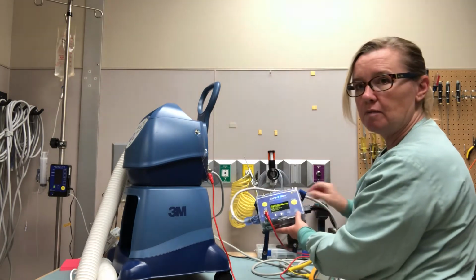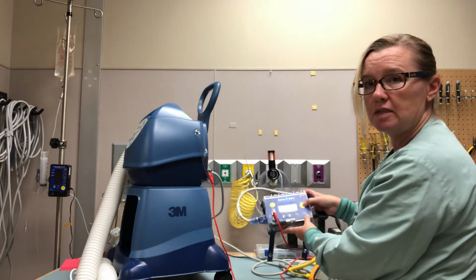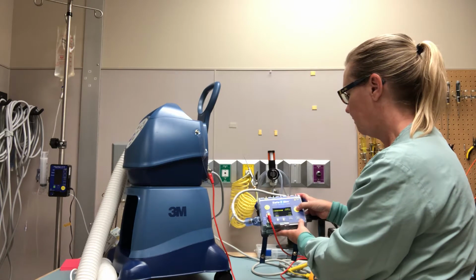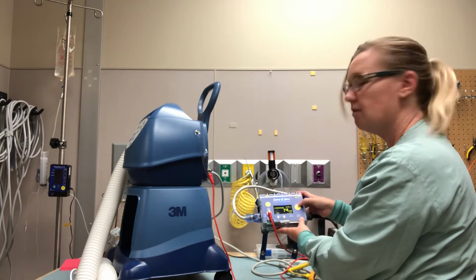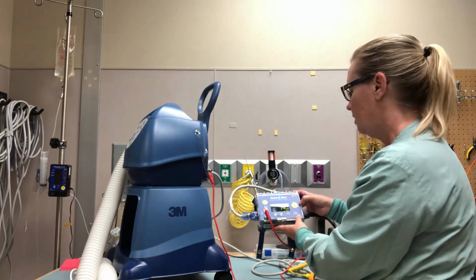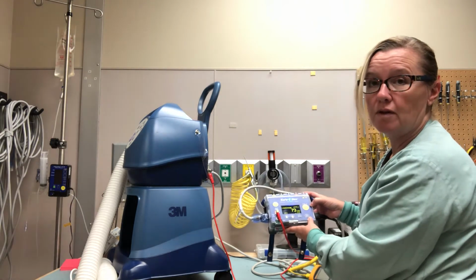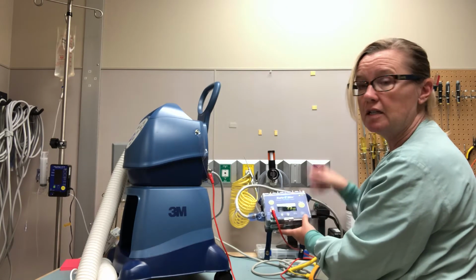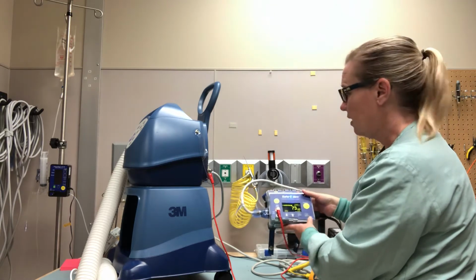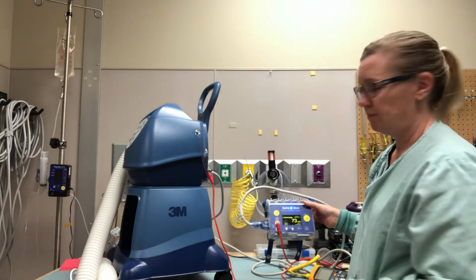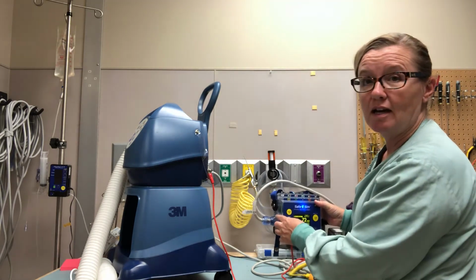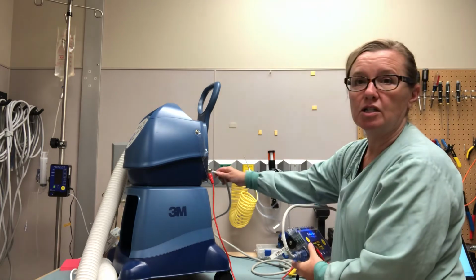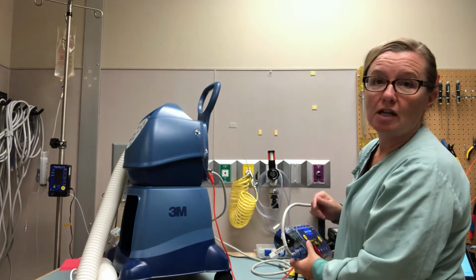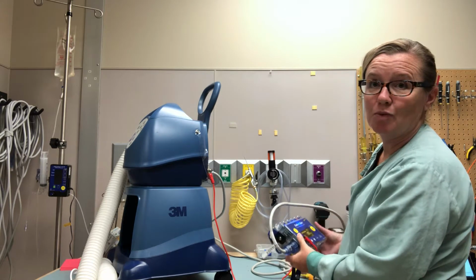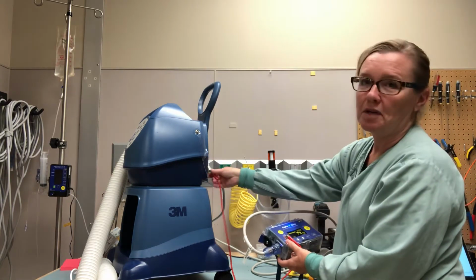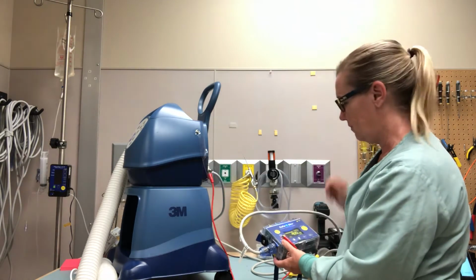I'm going to go ahead and run through my tests here. First, I'm going to do ground resistance. And I'm getting 74 milliohms. Now the standards are half an ohm or 500 milliohms, so we're well below that. If I did get a higher ground reading than what I would like, then the first thing I do is check the power cord. There may be a loose ground pin on this end, or maybe just a poor connection at the equipment. So the first thing is to always look at your power cord when you have ground resistance problems. And of course you want to make sure you have a good ground connection for your test lead.